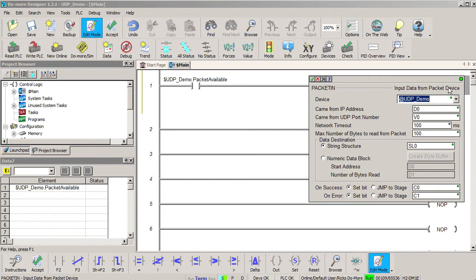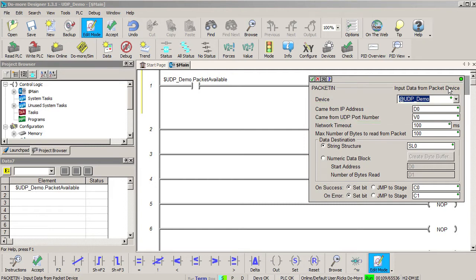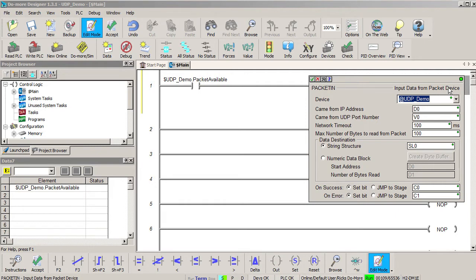When a packet is received, it has the sender's IP address and UDP port in the message. Those will get put in whatever variables we put here. You can then use those in your ladder code to filter out the messages. Maybe you need to respond to messages from one IP address differently than messages from another IP address, or maybe you need to respond differently to messages from one port versus another port.